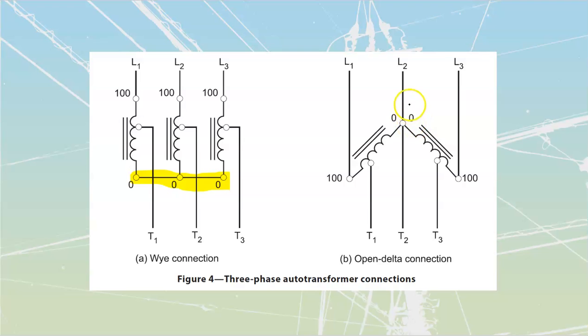But that open delta starter does have a little bit of an issue in that it can cause imbalances on the phase voltages on my line side, because I'm going to have current flowing through here and here and here and here, but I don't so much have current traveling across from here, right? This one, if you remember dealing with open deltas, we saw that we had both of those currents adding into these, whereas we've only got a single current going up each of those other 2 lines. On small motors, not a big deal, but if it's a really large installation, it can be significant enough to cause disturbances.